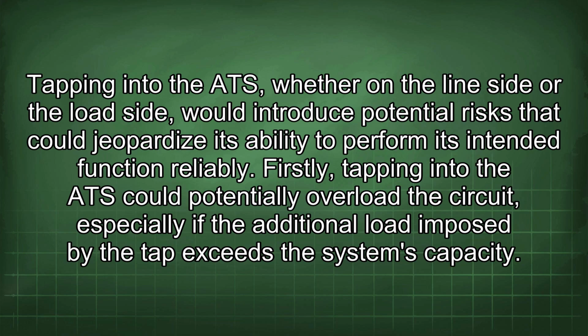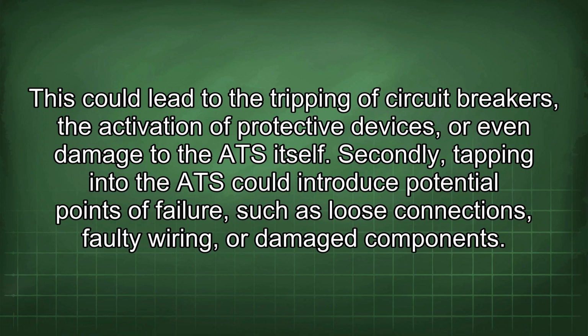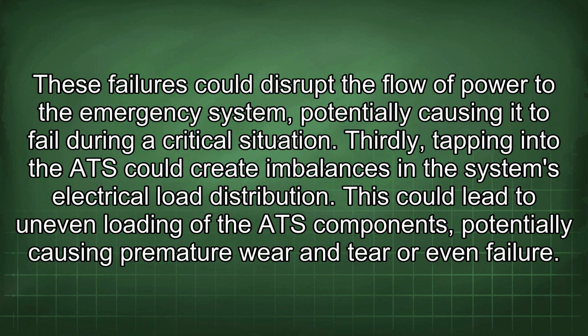Firstly, tapping into the ATS could potentially overload the circuit, especially if the additional load imposed by the tap exceeds the system's capacity. This could lead to the tripping of circuit breakers, the activation of protective devices, or even damage to the ATS itself. Secondly, tapping into the ATS could introduce potential points of failure, such as loose connections, faulty wiring, or damaged components. These failures could disrupt the flow of power to the emergency system, potentially causing it to fail during a critical situation. Thirdly, tapping into the ATS could create imbalances in the system's electrical load distribution. This could lead to uneven loading of the ATS components, potentially causing premature wear and tear or even failure.